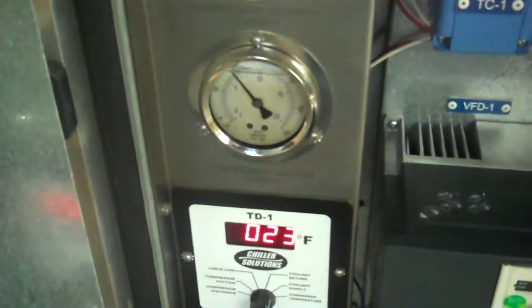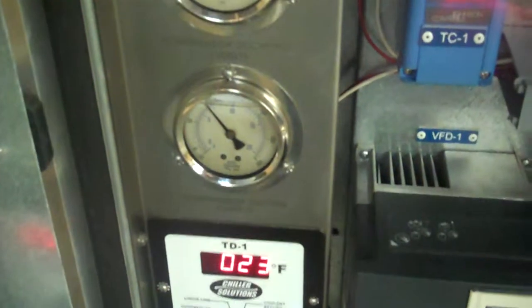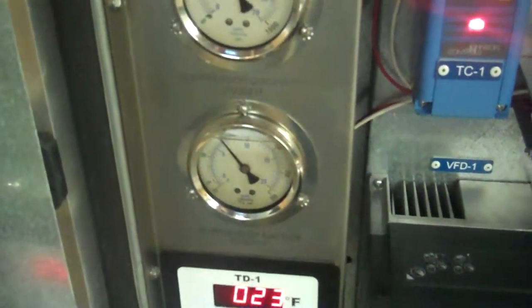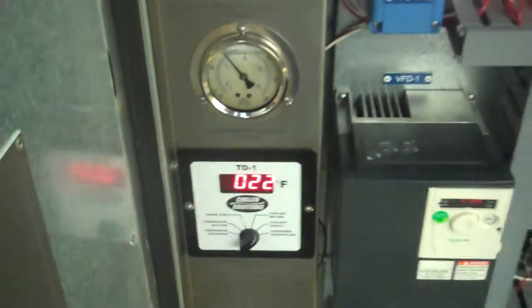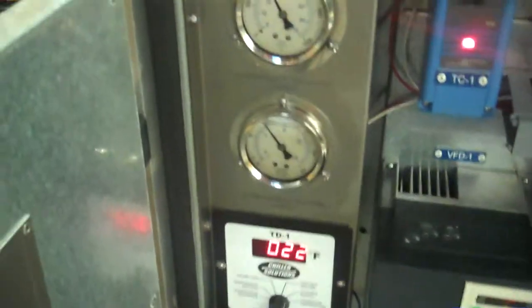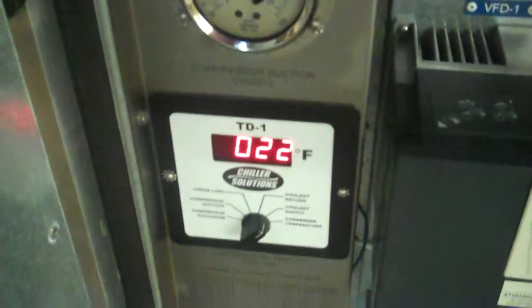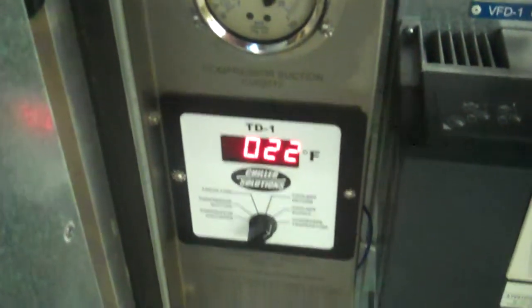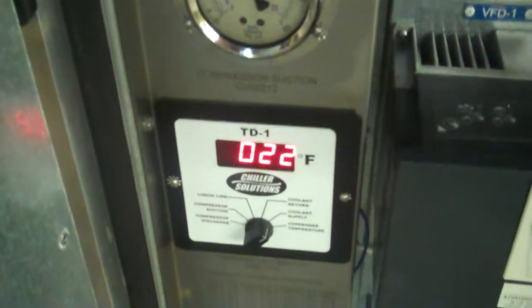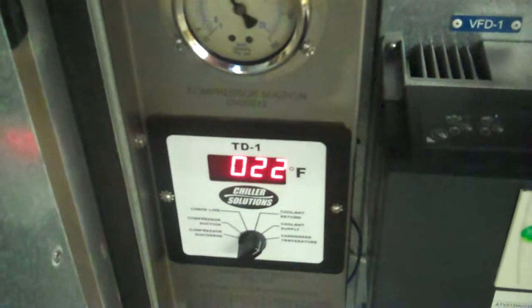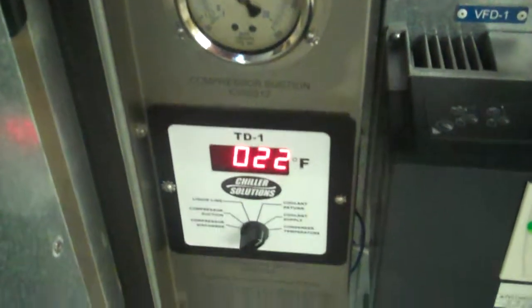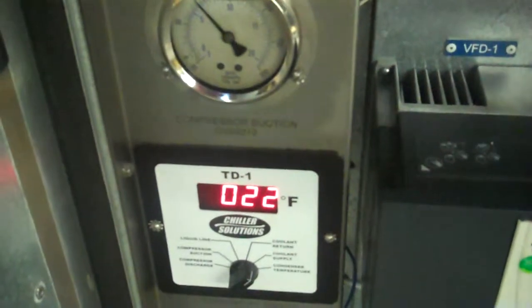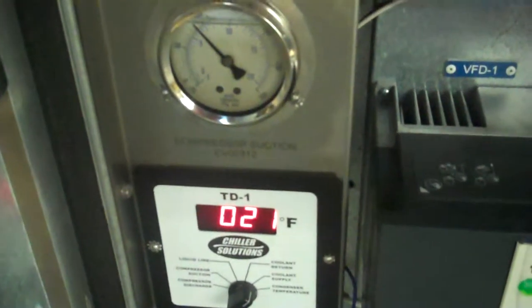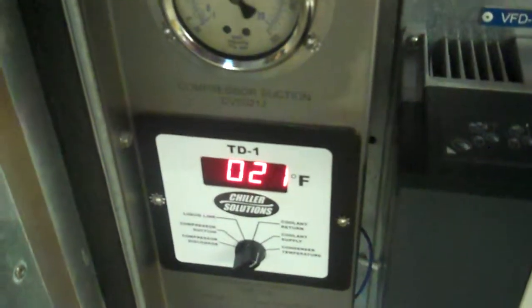I think we got about another 60 seconds of video here, and hopefully that's enough time for us to show it cycle a second time here, which is what you want to see. And depending on your load, you may hear the compressor on almost all the time. I can't remember the capacity of the reservoir tank. That helps you if you are oversizing this unit a little bit. It looks to be about a 45-gallon reservoir tank, cylindrical, pressurized, and insulated.